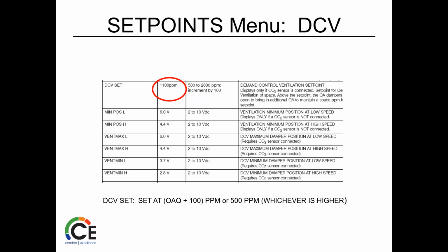So the set points menu contains 16 parameters. The factory default values for 15 of these are fairly straightforward. The parameter for DCV, or demand control ventilation set, should be modified from the default value to enable that if you need it. Again, that's information that you probably want before. The value for this parameter should be higher than the outdoor ambient CO2 level.